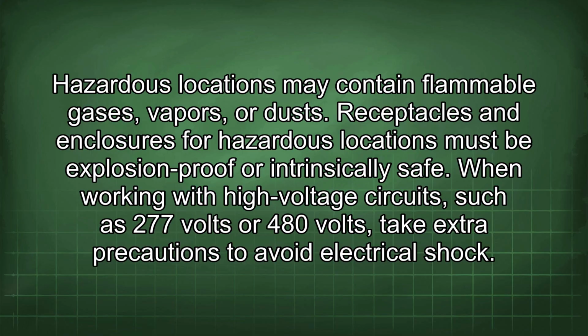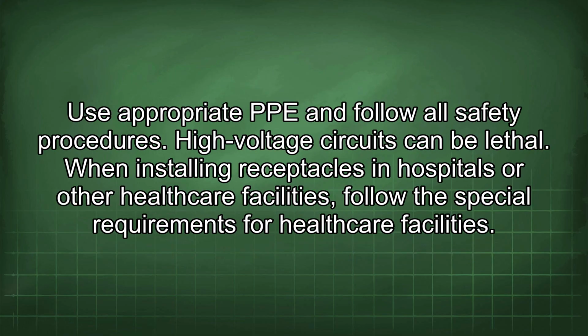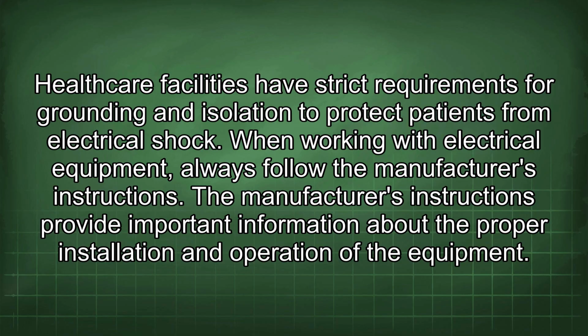When working with high-voltage circuits, such as 277 volts or 480 volts, take extra precautions to avoid electrical shock. Use appropriate PPE and follow all safety procedures. High-voltage circuits can be lethal. When installing receptacles in hospitals or other healthcare facilities, follow the special requirements for healthcare facilities. Healthcare facilities have strict requirements for grounding and isolation to protect patients from electrical shock.